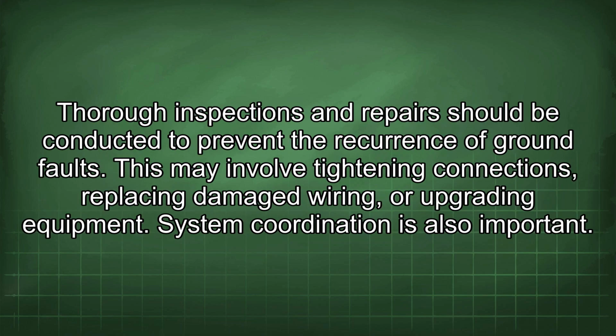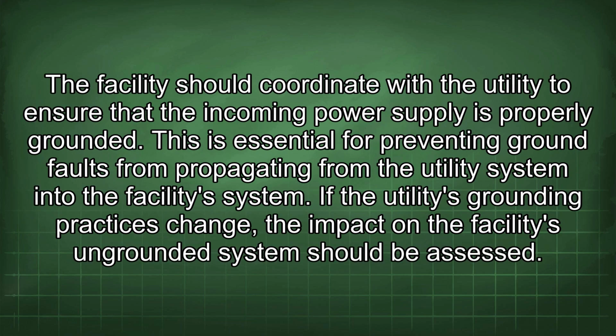Thorough inspections and repairs should be conducted to prevent the recurrence of ground faults. This may involve tightening connections, replacing damaged wiring, or upgrading equipment. System coordination is also important. The facility should coordinate with the utility to ensure that the incoming power supply is properly grounded. This is essential for preventing ground faults from propagating from the utility system into the facility's system.